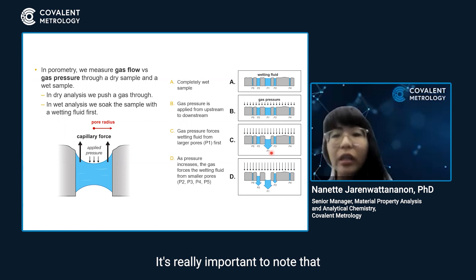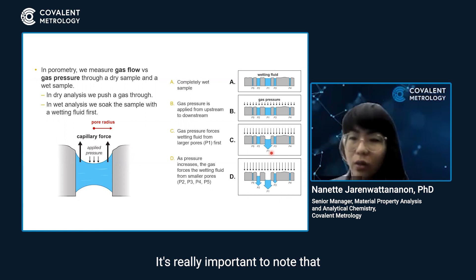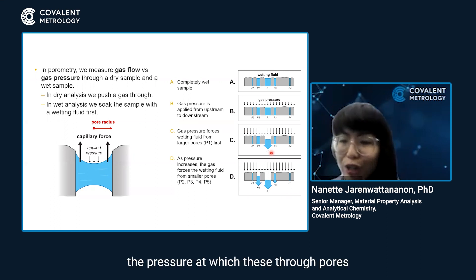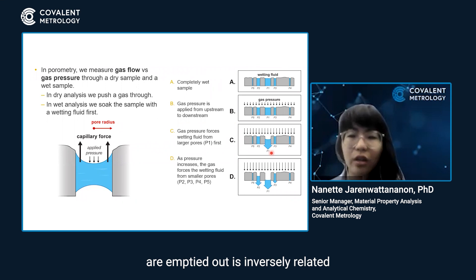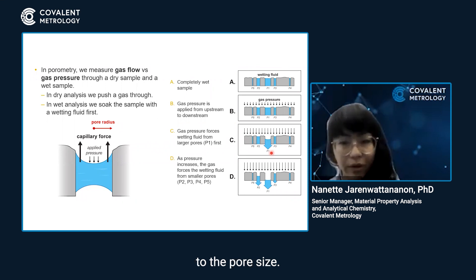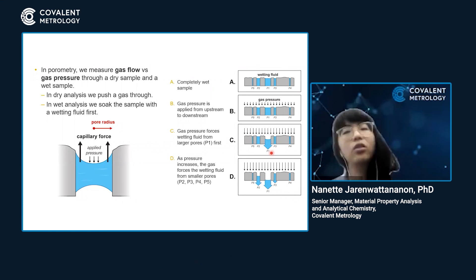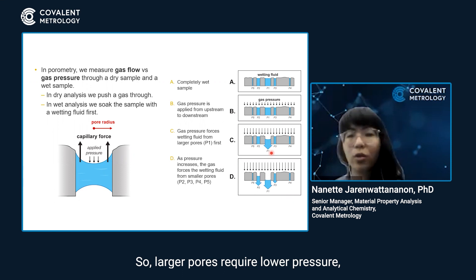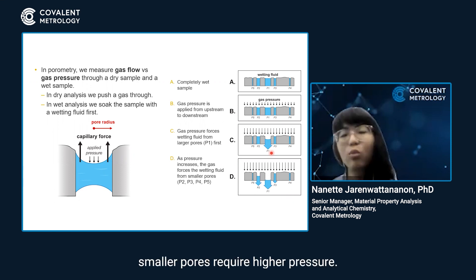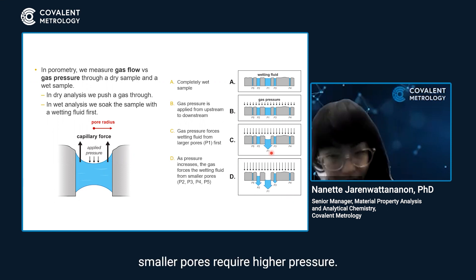It's really important to note that the pressure at which these through pores are emptied out is inversely related to the pore size. So larger pores require lower pressure, and smaller pores require higher pressure.